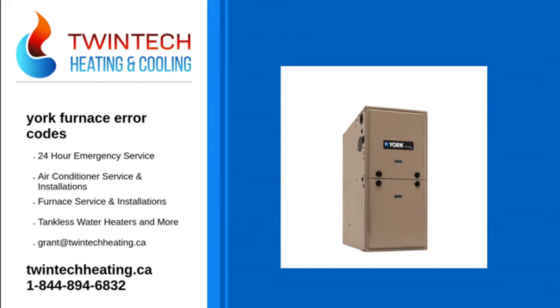Code: 7 red flashes. Result: this fault code indicates that the flame could not be established. This no light condition occurred 3 times (2 retries) during the call for heat before locking out. Low gas pressure, faulty gas valve, dirty or faulty flame sensor, faulty hot surface igniter, or burner problem may cause this. The furnace will lock out for 1 hour and then restart.